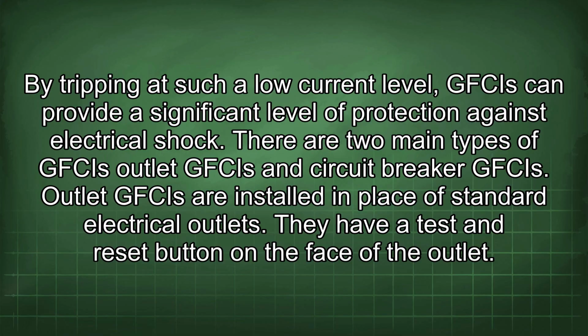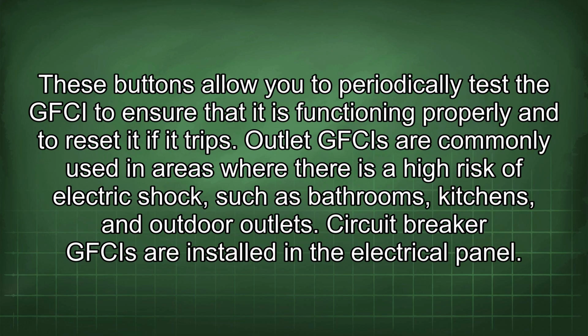There are two main types of GFCIs: outlet GFCIs and circuit breaker GFCIs. Outlet GFCIs are installed in place of standard electrical outlets. They have a test and reset button on the face of the outlet. These buttons allow you to periodically test the GFCI to ensure that it is functioning properly and to reset it if it trips.